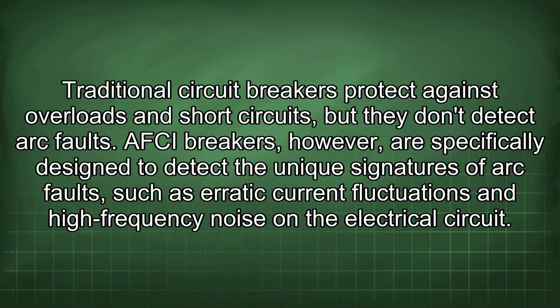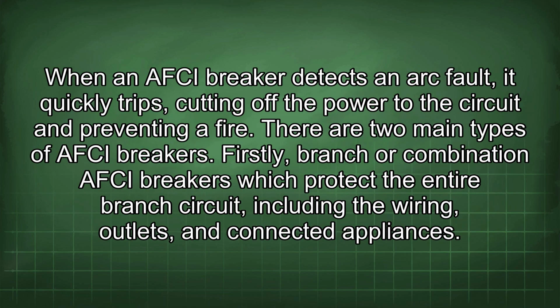Traditional circuit breakers protect against overloads and short circuits, but they don't detect arc faults. AFCI breakers, however, are specifically designed to detect the unique signatures of arc faults, such as erratic current fluctuations and high-frequency noise on the electrical circuit. When an AFCI breaker detects an arc fault, it quickly trips, cutting off the power to the circuit and preventing a fire. There are two main types of AFCI breakers.